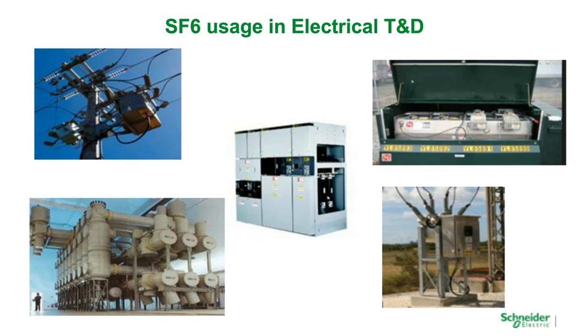So for starters, you have some high voltage switchgear on this. You have station breaker, pad mounted switchgear, recloser, and in the middle we also have Square D's HVLCC metal enclosed switch. So the main objective of this slide that I want to propose is that we use it in a lot of different areas, but not all of these items are considered gas-insulated switchgear. In fact, only one of these is not gas-insulated switchgear, and that's the HVLCC. I'll get into a little more detail about why HVLCC is not GIS and what makes these other products gas-insulated gear. We'll get into that in a couple more slides, so we'll move on.